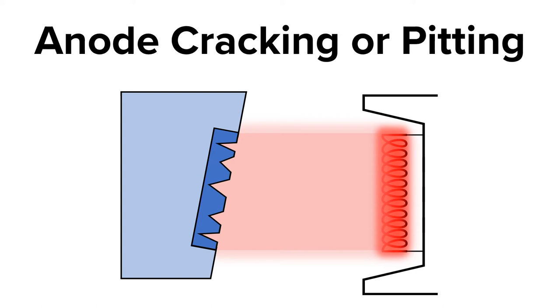Another reason the anode might crack or pit is due to long exposures at high MA. A rotating anode can reach temperatures of over 5,000 degrees Fahrenheit. That prolonged heat can cause micro-cracking, which increases tungsten target evaporation onto the glass.